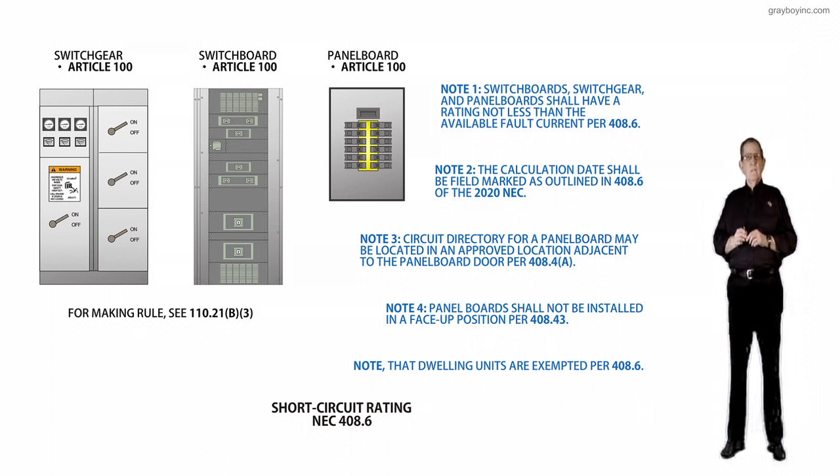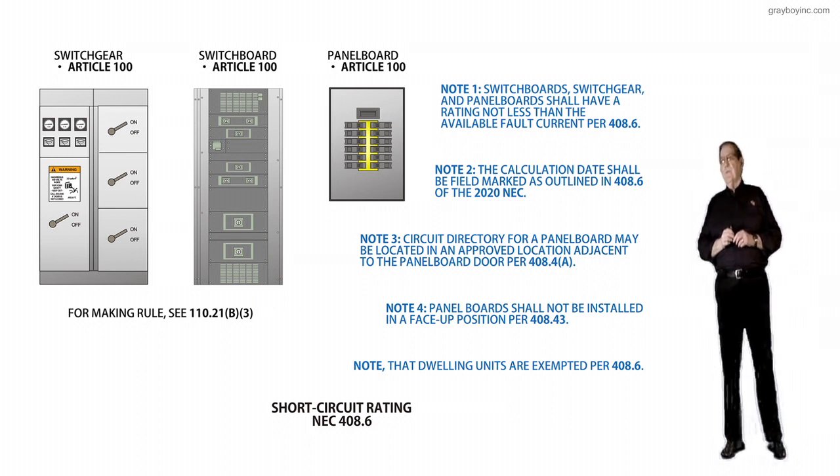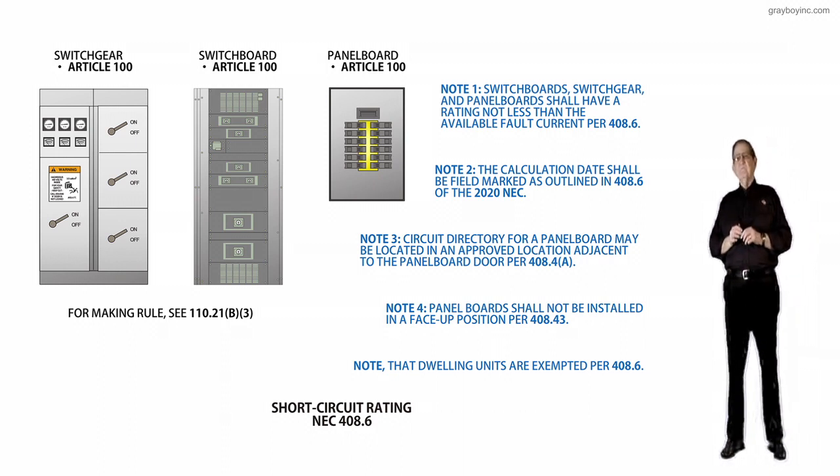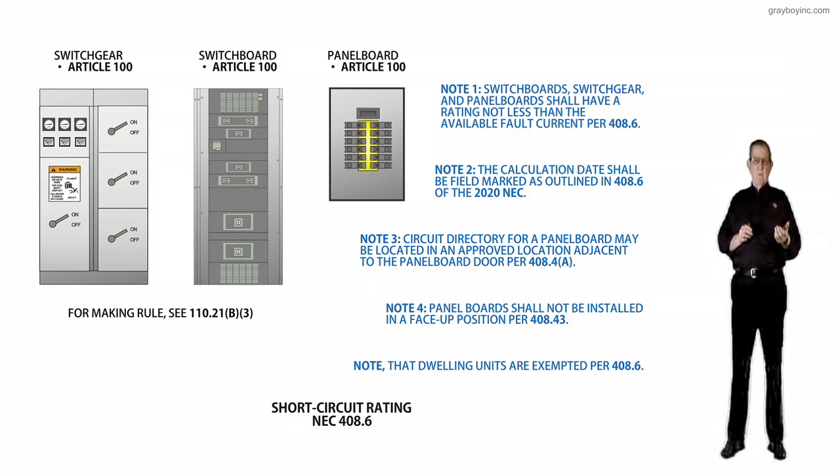And I kind of addressed that to you earlier in the presentation, that the reason this is required or mentioned is that we used to take like a 10 kA breaker and take 80% of that 10 kA, and we'd only hit it with 8,000 amps.